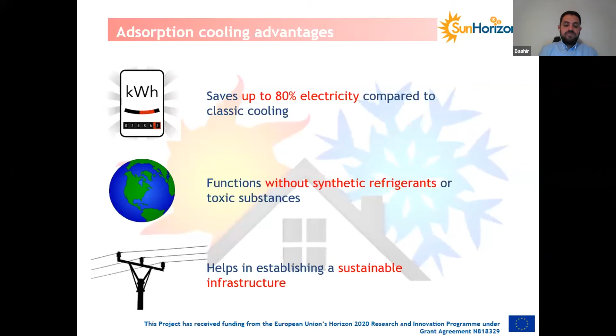Today I will be speaking about our hybrid solution that combines adsorption technology with conventional compression. Let's first start with the adsorption part. As I said, it is driven by heat instead of electricity, which leads to savings of up to 80% or more in electricity compared to conventional state-of-the-art compression cooling. We use water as a refrigerant, so there are no synthetic refrigerants in the machines, and there are no moving parts inside the modules, which simplifies the process and helps establish a sustainable infrastructure.